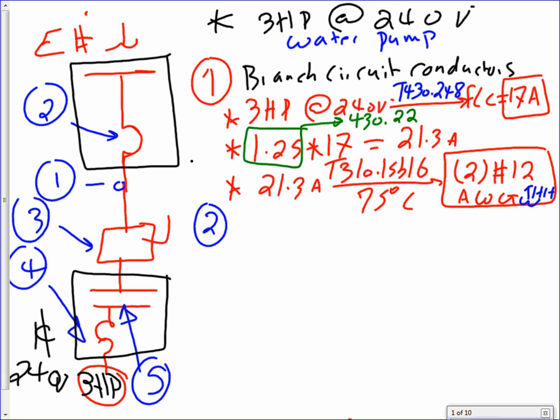Cool. Any questions, guys, about the branch circuit? Now we have 2 conductors. Are you going to put them in a cable or in a conduit? Your choice. That could be an NM cable, number 12 conductor. No, it has to be a UF cable in order to get the W in it. A UF cable, 12-2, you bury it and go all the way to the pump, done. Or it could be 2 THHW conductors in a conduit, sized appropriately.